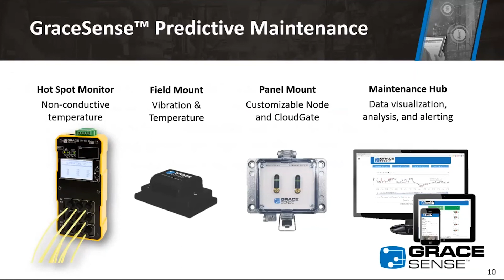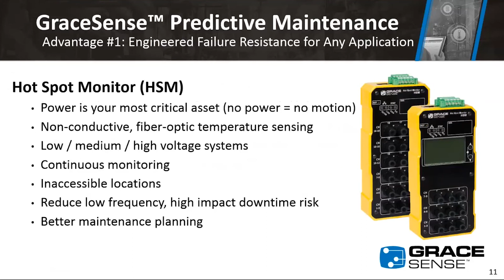A bit more on the hotspot monitor: this type of device is used in a low frequency, high impact type area. You'll have switchgear that runs for years and years without a problem, but when there is a problem, all motion in your facility is shut down. So it's definitely for those critical pieces of equipment. The big benefit is continuous monitoring as well as a view of inaccessible locations, which I'll show in a second.